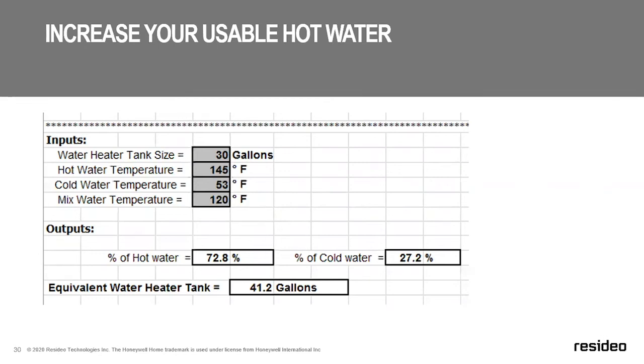So now if you put a mixing valve on it, this is just one example, and this is an Excel spreadsheet snapshot where the gray numbers and boxes up there are your inputs. So let's say we had a 40-gallon, it failed, we can't get a new 40-gallon to go in because the insulation is too big.